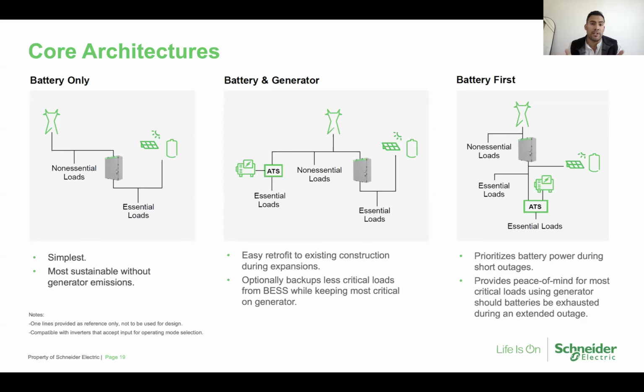Then we go to the middle here. We have a battery and generator system where you have an automatic transfer switch and a Source Pack product that both operate independently. So think of it: utility, main switchboard, downstream you have your ATS providing emergency power to your Article 700 loads. This can be fire pumps, elevators, things like that, where you want to have that equipment on emergency generator power. And then you have your automatic interconnection switch, or what we call Source Pack, connected to your battery energy storage system, where in the event of an outage, you're disconnecting that battery system from your main switchboard and isolating those essential loads to provide backup power. So again, this works great for retrofits if you want to add a PV energy storage system into your facility, but you don't want to add all custom switchboard or control.